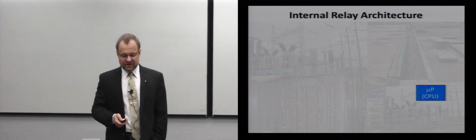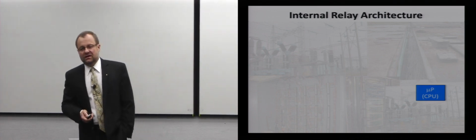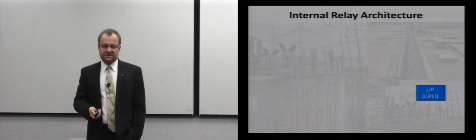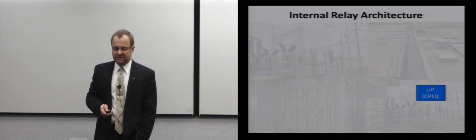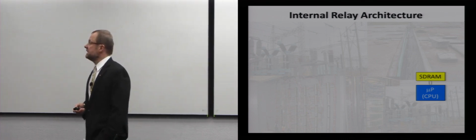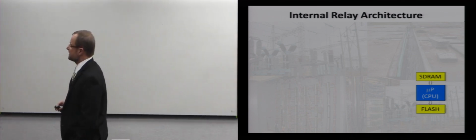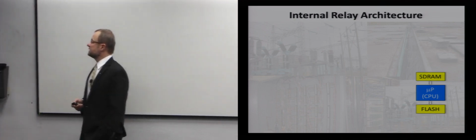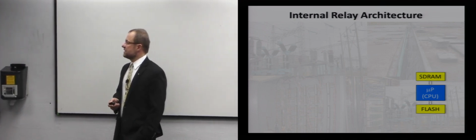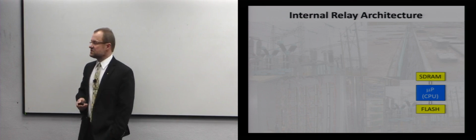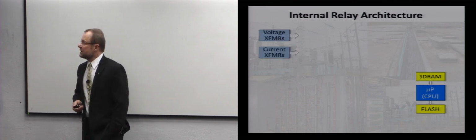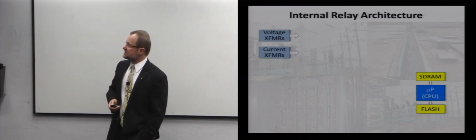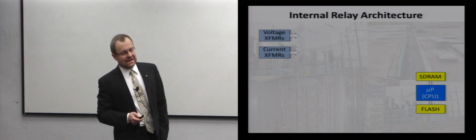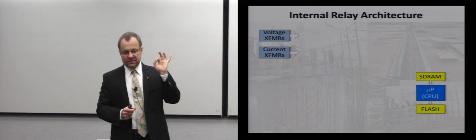So what is the typical architecture on the inside? A microprocessor relay needs a microprocessor. So, okay, we have at least one, let's call it CPU. This thing needs to have memory to operate. Typically, that's non-volatile memory, lots of it for storing records. You have interposing transformers for voltage and current. Those are inside the box. Those are relatively small. And the reason we have them is for galvanic isolation.